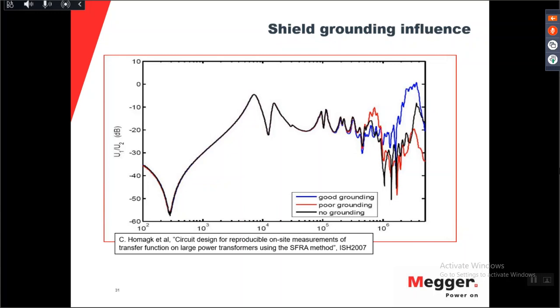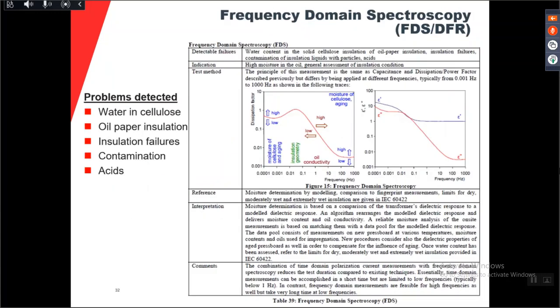With that, we go to the SFRA, or sorry, the FDS. Some also call this DFR, frequency domain spectroscopy, which is the FDS. DFR is the dielectric frequency response. This one is used to find water in cellulose, in oil-paper insulation. You can see insulation failures, you can see contamination, and you can see acid. You usually get an indication from high moisture in the oil.